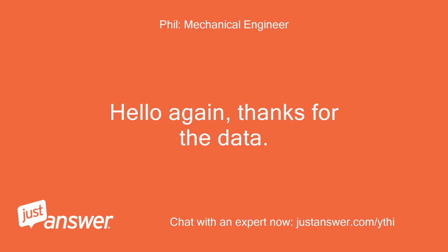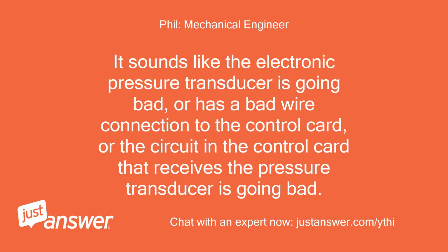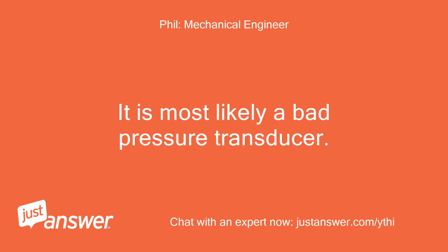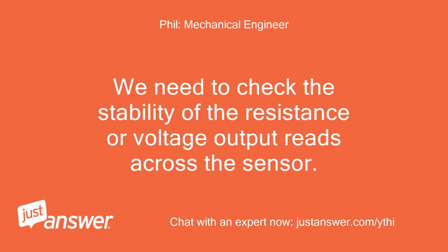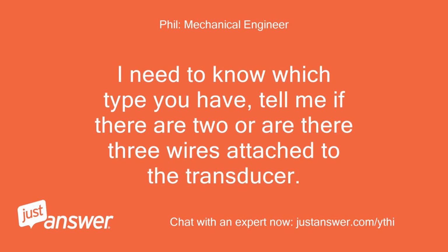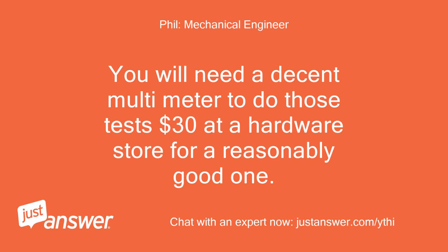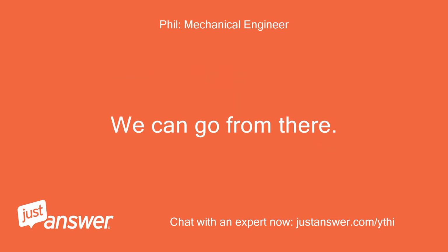Thanks for the data. It sounds like the electronic pressure transducer is going bad, or has a bad wire connection to the control card, or the circuit in the control card that receives the pressure transducer is going bad. It is most likely a bad pressure transducer. We need to check the stability of the resistance or voltage output reads across the sensor. I need to know which type you have. Tell me if there are 2 or 3 wires attached to the transducer. You will need a decent multimeter to do those tests. $30 at a hardware store for a reasonably good one. We can go from there.